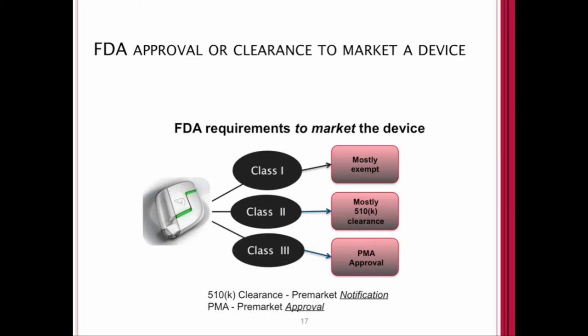FDA approval or clearance to market a device: for class one devices, they are mostly exempt from the FDA approval process. Most class two devices go through the 510K process, though some class two devices are exempt from the 510K process. Class three devices do require PMA approval. Since class three devices have the most risk to patients, you have to go through the most rigorous approval process — pre-market approval. These applications are quite onerous and require many volumes of information.